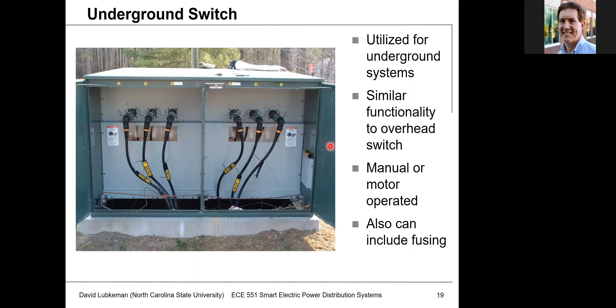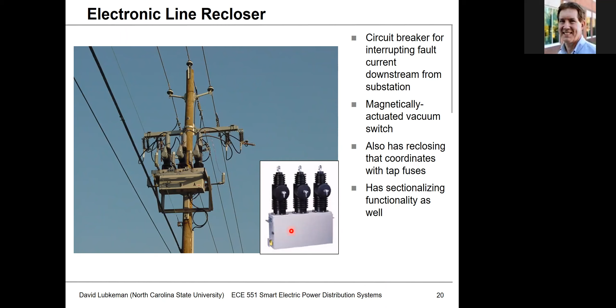Now, once you get outside the substation, if you want to have protection and you want to be able to clear a fault current, then what you're going to need is what's called a recloser. It's called a recloser because these devices are set up where if they detect a fault, they'll clear the fault, but then they might close in a short time later because many of these faults are going to be temporary in nature. These reclosers usually consist of 3 independent poles, and these poles could actually be controlled separately. So you could do independent phase control in the field. You typically won't do this in a substation because of 3-phase load, but when you're closer to the residential customers, you can do your operations on a single phase basis. And so these are going to be magnetically controlled switches where you have a mechanism in this cabinet which controls each individual pole.